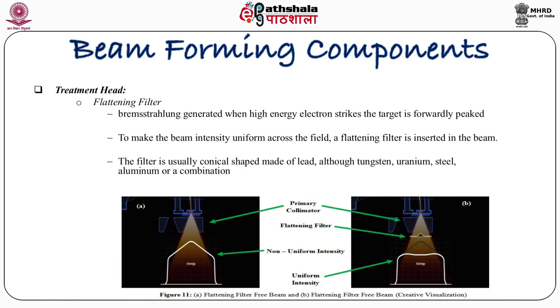For treatment purposes, we want a uniform dose on a particular surface or at different depths on the patient surface. But the output contains a peak in the center. We want to flatten it — that is why a flattening filter is used, which absorbs the most probable energies and makes the beam flat. This flattening filter is introduced in the treatment head.